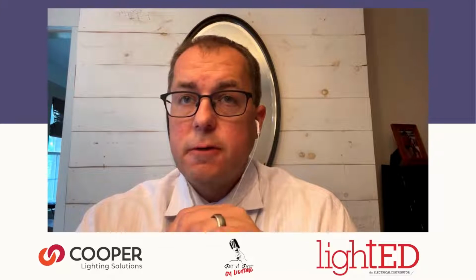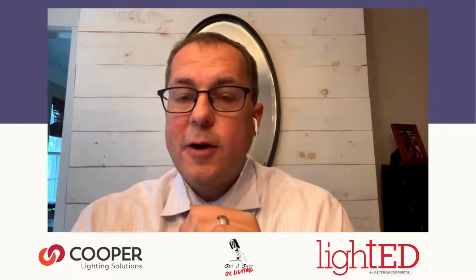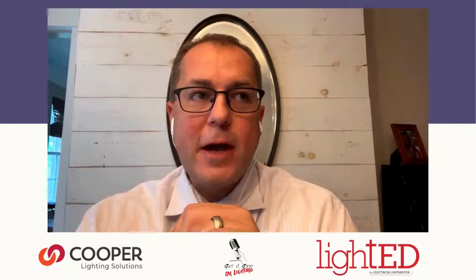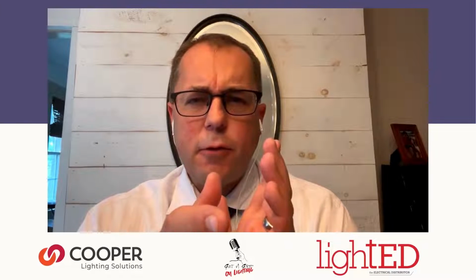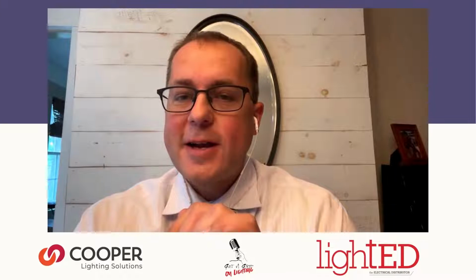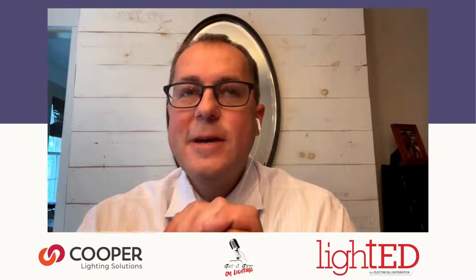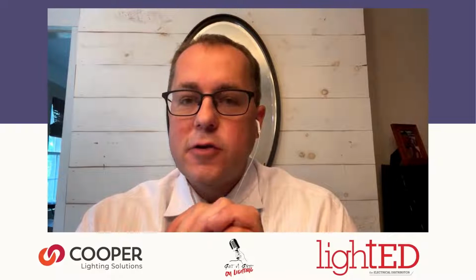The challenge is there are different versions of BACnet. Recently I was on a project where it said BACnet, but it was, I think, BACnet version 2, and we're at BACnet 14. So just because they claim it's BACnet doesn't mean it's perfectly universal. I'd say the integration is still the struggle.